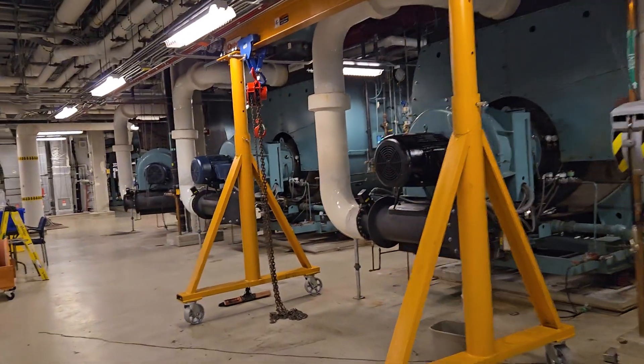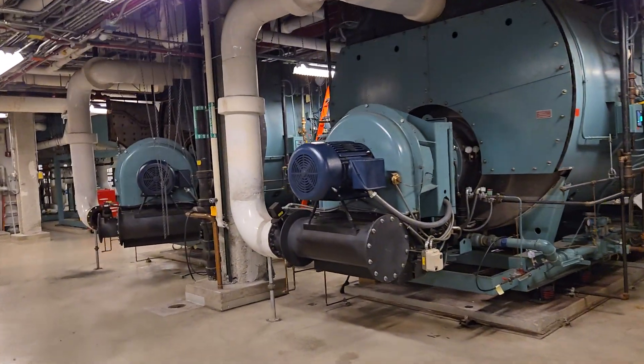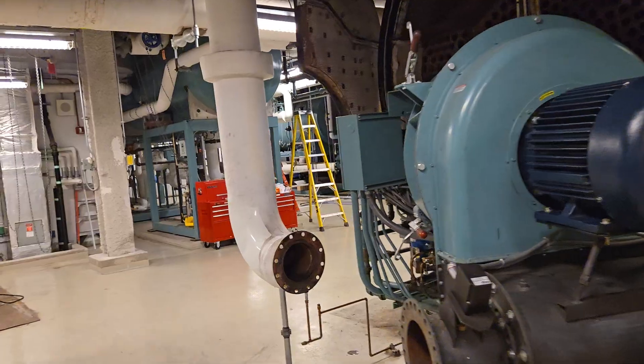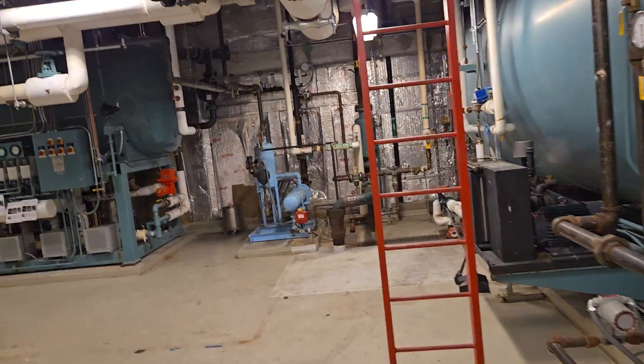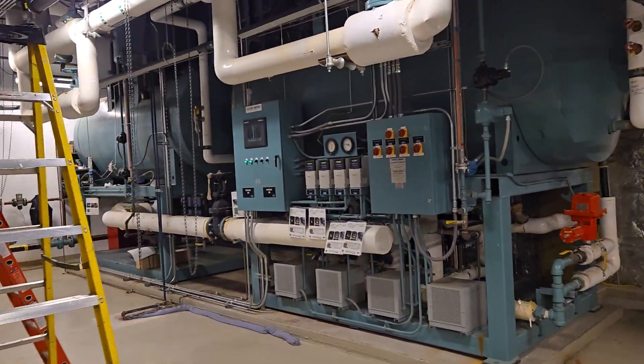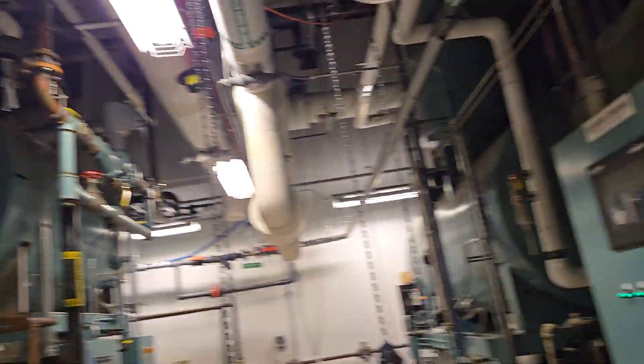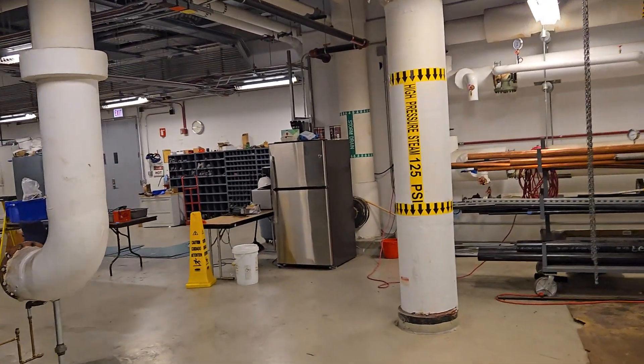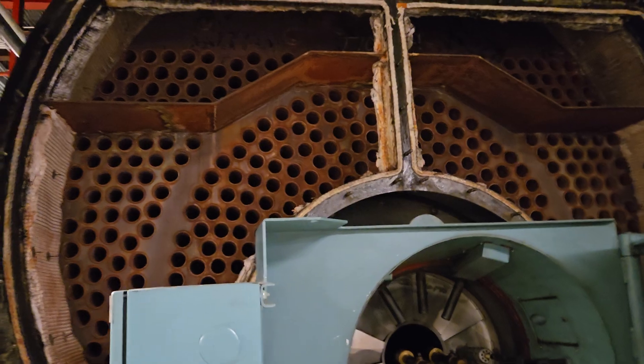Sterilization and things like that — so that's this room. That's a lot of firepower for wintertime because we have to heat everything with these boilers. They heat water and pump it through the building. Here are the big tanks that accept return water from the building and reheat it — those are surge tanks. These are deaerator tanks; they take the oxygen out of the water because it causes oxidation inside the boiler, and we don't want that inside those tubes.